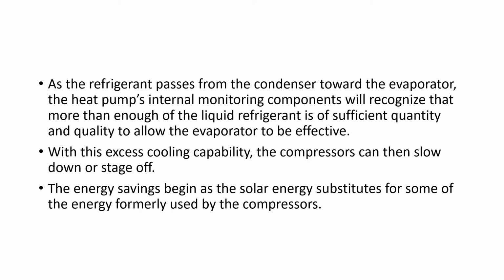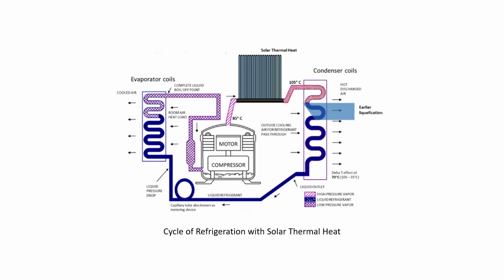As the refrigerant passes from the condenser toward the evaporator, the heat pump's internal monitoring components will recognize that more than enough of the liquid refrigerant is of sufficient quantity and quality to allow the evaporator to be effective. With this excess cooling capability, the compressor can then slow down or stage off. The energy saving begins as the solar energy substitutes for some of the energy formerly used by the compressors. So this picture shows the cycle of refrigeration with solar thermal heat.